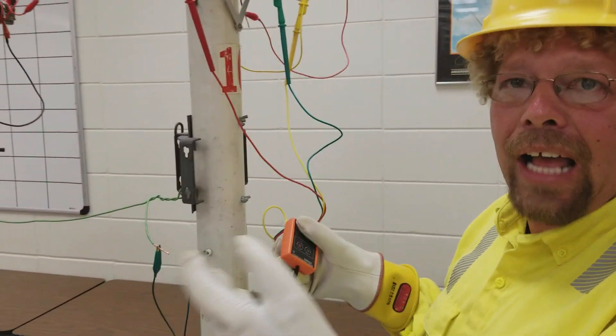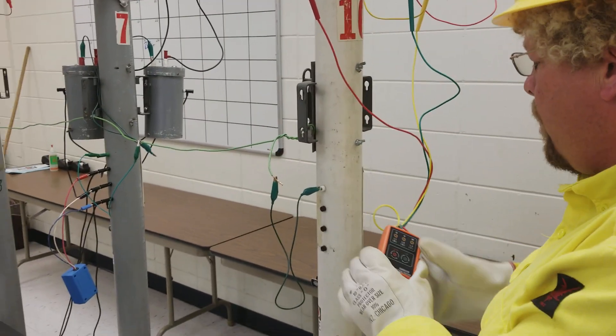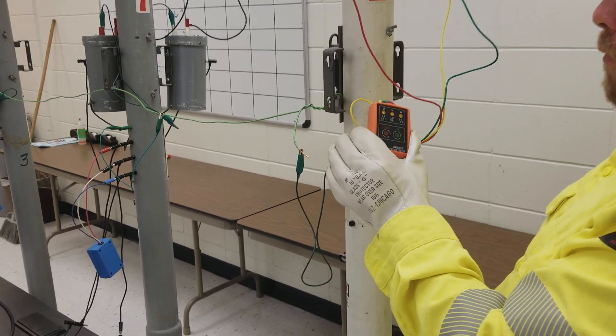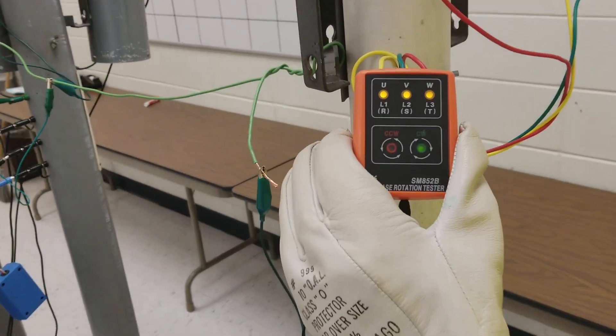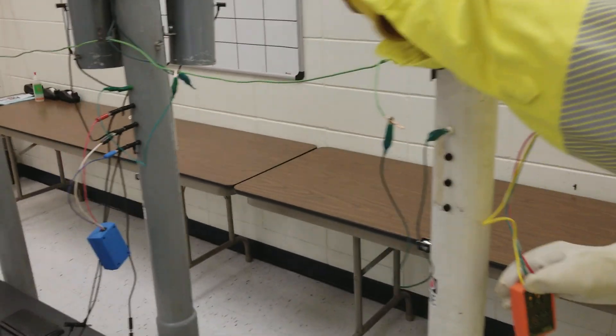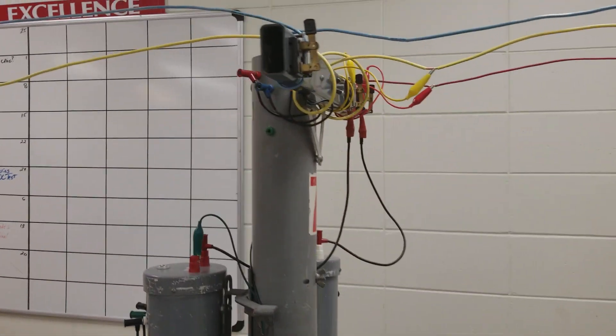Wild leg, stinger, high leg, whatever you call it. People call it a lot of different names. So this is our primary coming in and we have a one, two, three rotation on the primary coming in. So we go through, everything is energized now. Both banks are energized.